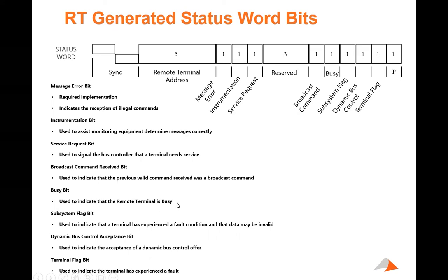Busy bit, it's used to indicate that the terminal is busy. In certain situations, it's really bad form to use the busy bit. Most of the time, the busy bit is used when the system is coming up and it's not fully operational yet. It would be very strange to implement that during a time that the system is supposed to be fully operational, and many people frown upon it.